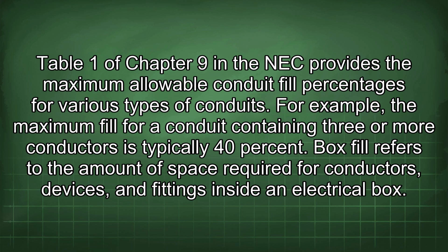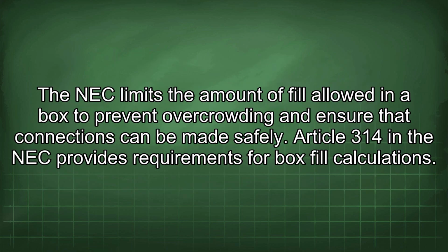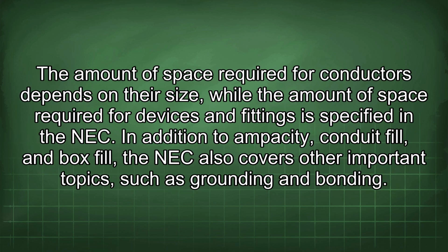Box fill refers to the amount of space required for conductors, devices, and fittings inside an electrical box. The NEC limits the amount of fill allowed in a box to prevent overcrowding and ensure that connections can be made safely. Article 314 in the NEC provides requirements for box fill calculations. The amount of space required for conductors depends on their size, while the amount of space required for devices and fittings is specified in the NEC.